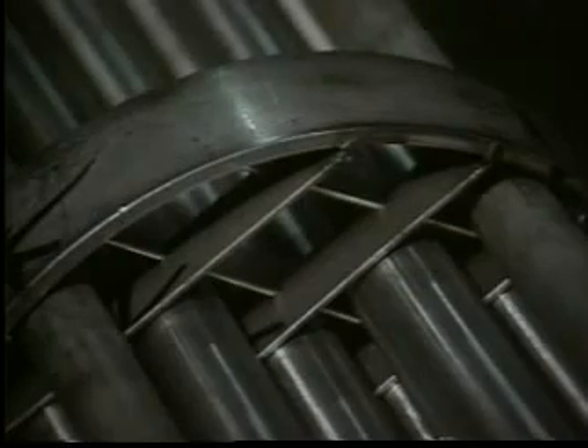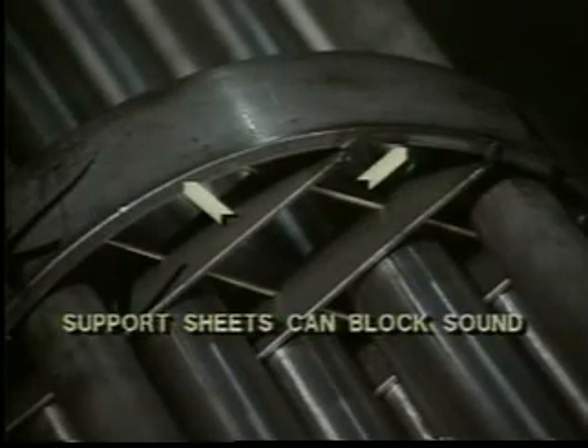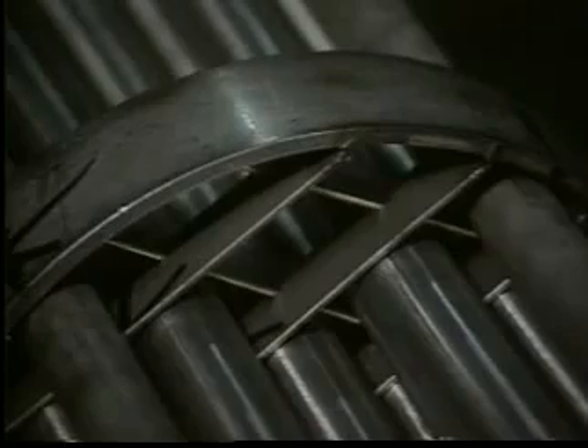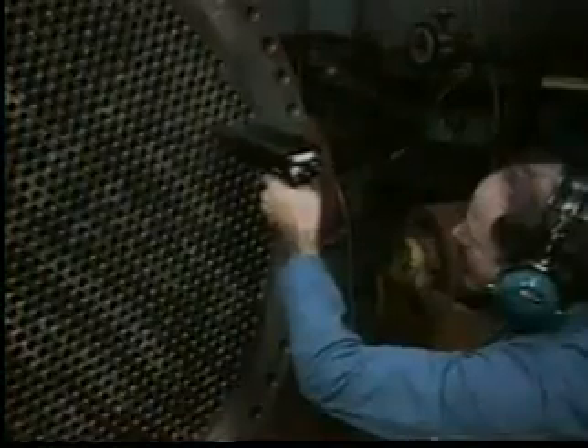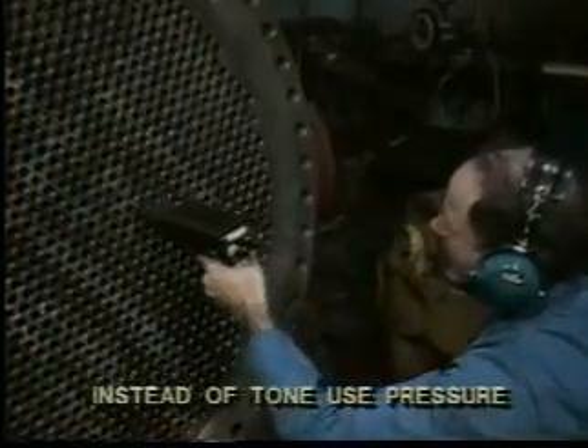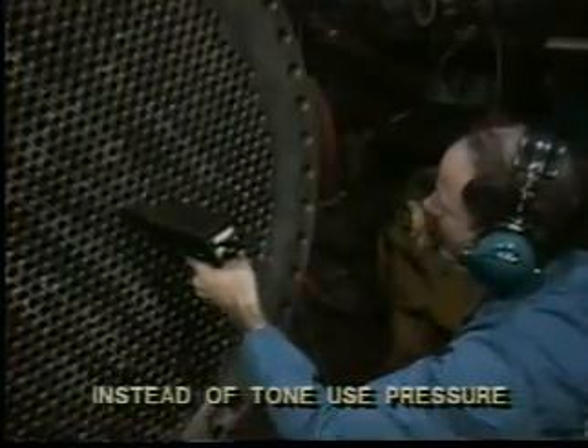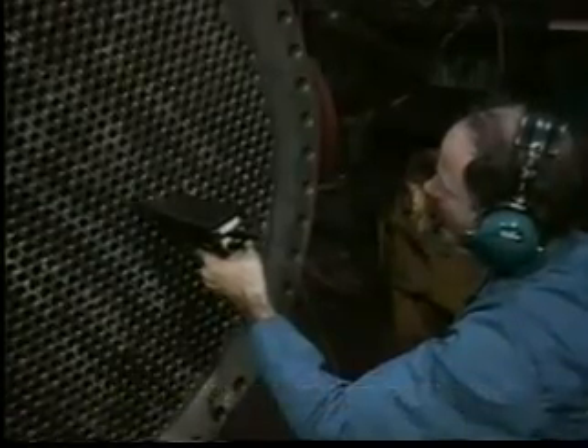The tone may also be blocked by baffles or support sheets. If more sound is needed, you may use more tone generators with existing fittings in the central area of the heat exchanger. Or you may create additional fittings for testing purposes if your company's policies permit. In certain situations, it may not be possible to use the tone method. In these instances, use the pressure method.